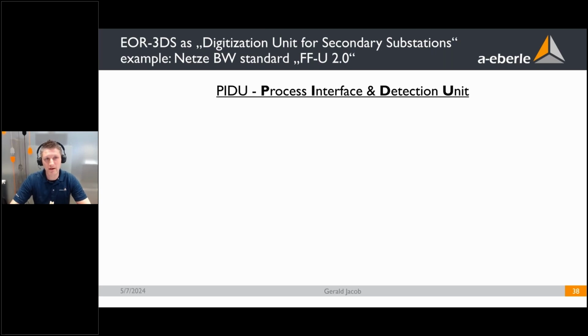Netze BW required in their tender a so-called PIDU device. This PIDU device means a process interface and detection unit. What does it mean? The detection unit is our device. Our device is an earth fault and short circuit indicator or detection device, but they wanted to have more, and this I want to explain here.